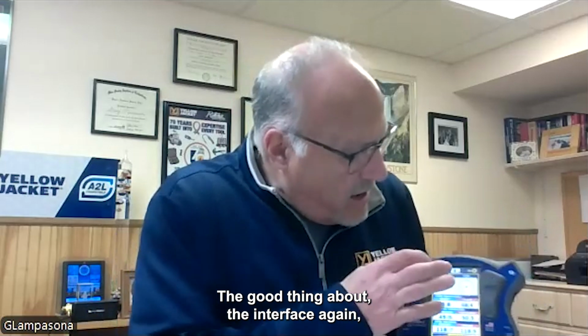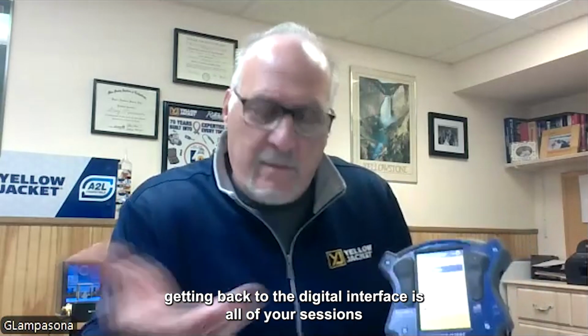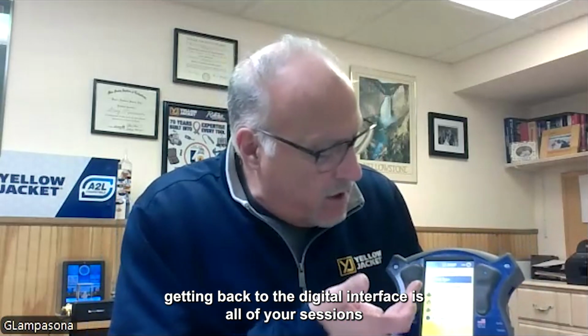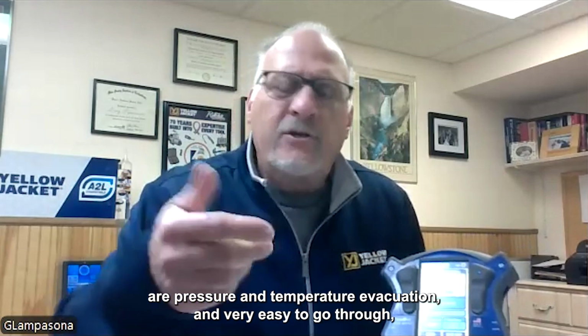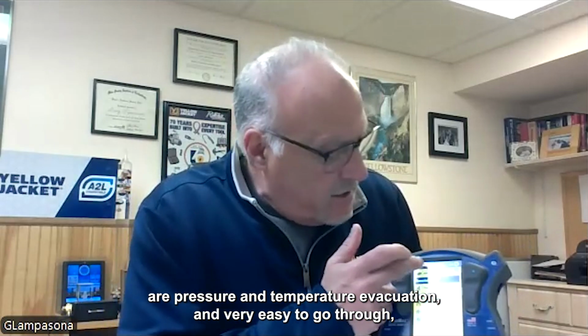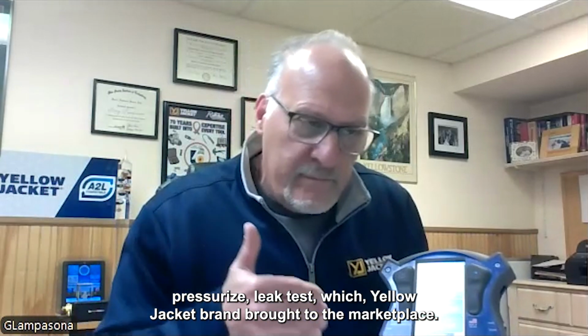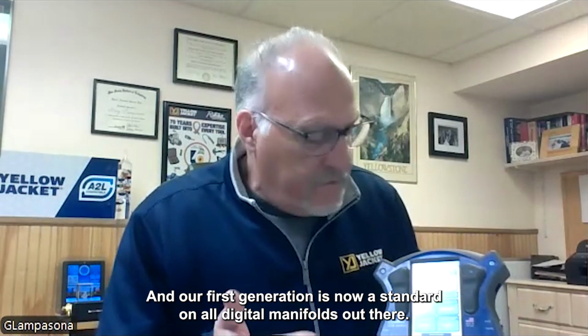The good thing about the interface, getting back to the digital interface, is all of your sessions are pressure and temperature evacuation, and very easy to go through. Pressurized leak test, which Yellow Jacket brand brought to the marketplace in our first generation, is now a standard on all digital manifolds out there.